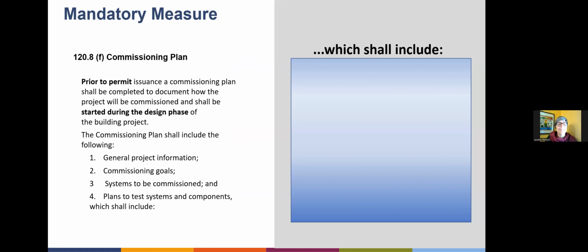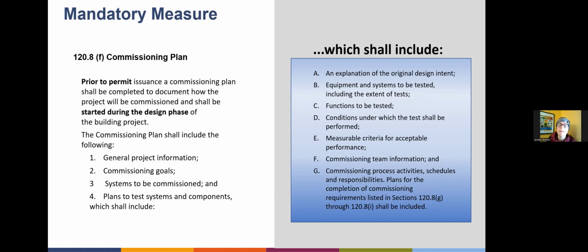The commissioning plan -- Andy just went over that, but back to what's actually spelled out in the code in section 120.8, the commissioning plan. It has to include general project information, commissioning goals, the systems to be commissioned, and it specifically addresses the plans for testing. Then it says which shall include, and now they list in the 2022 code what you are supposed to include in that commissioning plan. Some of the biggest things Andy mentioned were the functions that are to be tested, conditions under which the test shall be performed, and measurable criteria for acceptable performance.